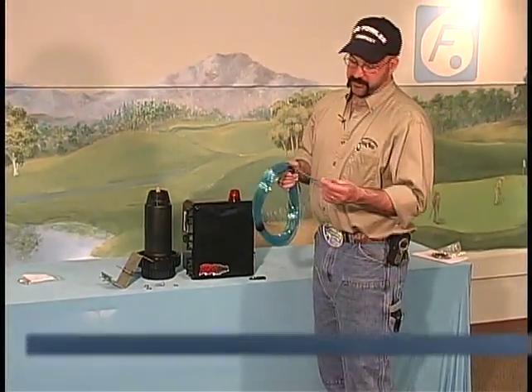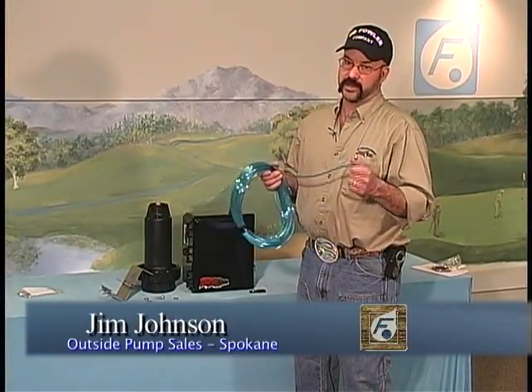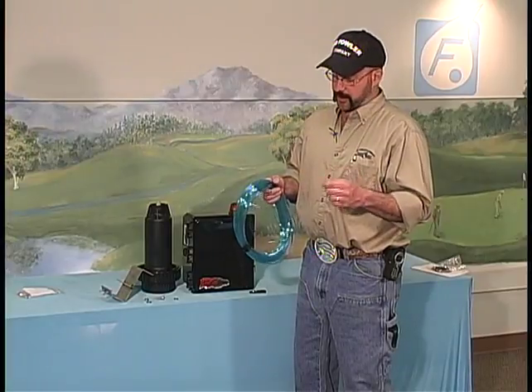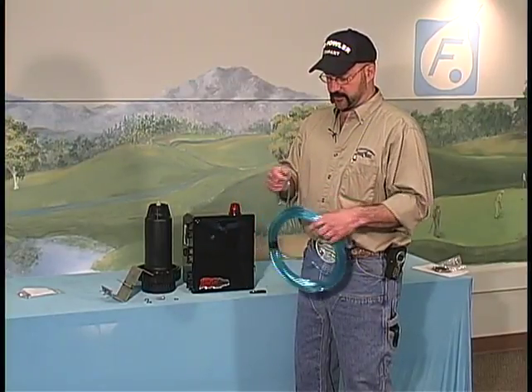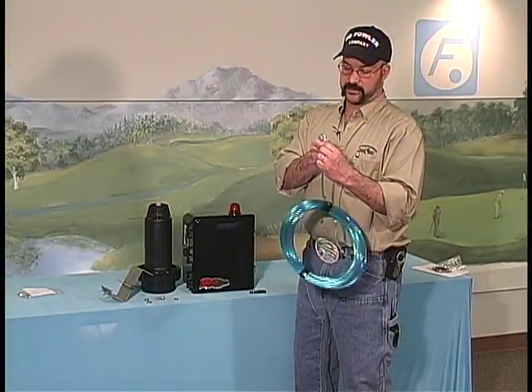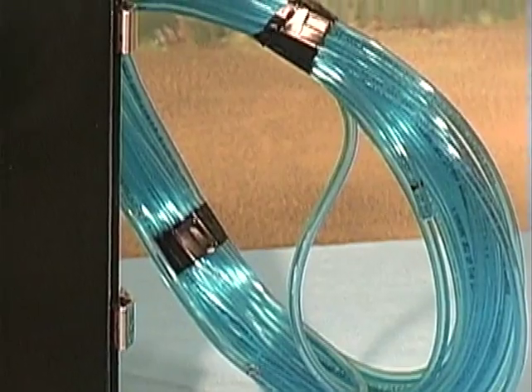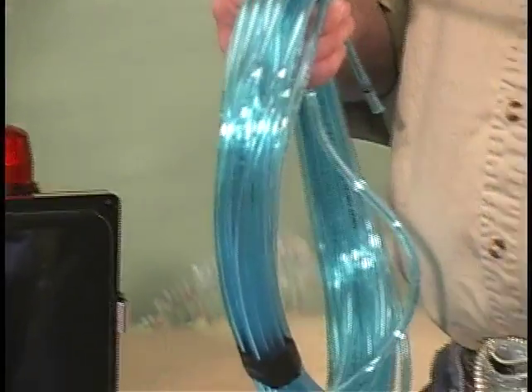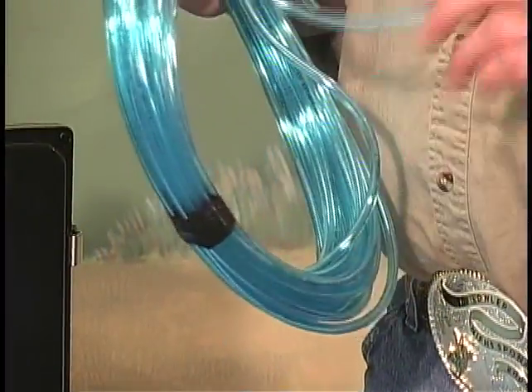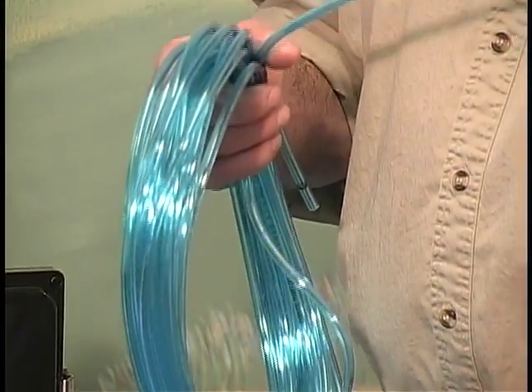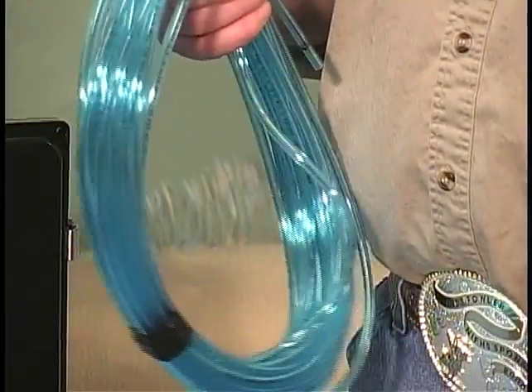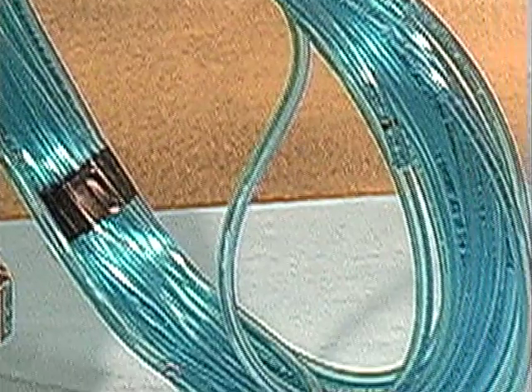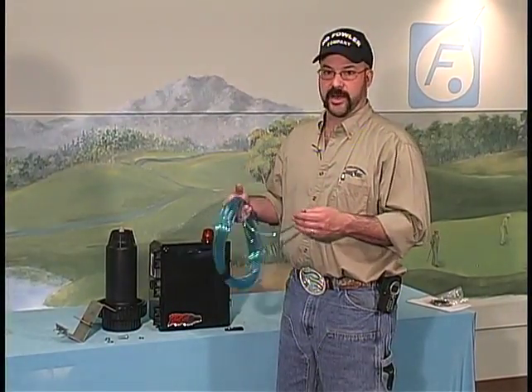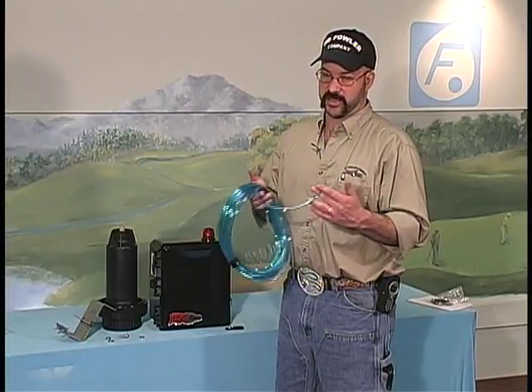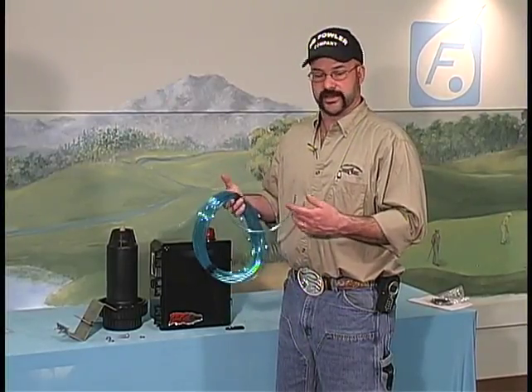The panel itself comes with 50 feet of tubing. If you need more than that, you can buy bulk tubing. There are installations where it's been run several hundred feet without affecting the operation of the panel. And the tubing is very tough, very difficult to kink. It should be the only tubing that you use. Anything that you substitute may kink a little easier than this. And we can get couplers for this. You should have left about 5 to 7 feet in the tank, depending on the depth of your stinger dropping down to your pressure bell, because that bell may need to come out for servicing at some point in the future, and you need to have enough tubing at the tank end of it to be able to pull that out and lay it down and be able to work on it.